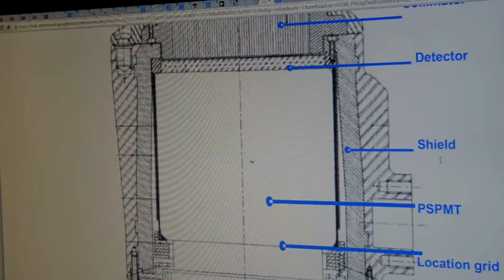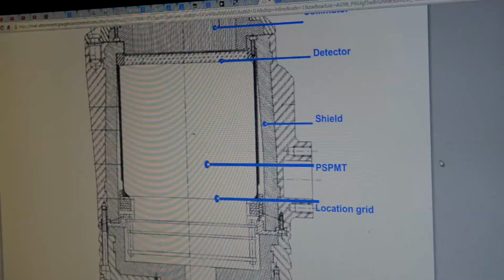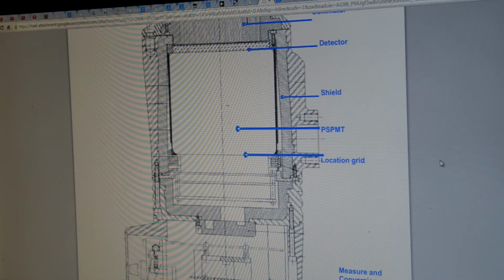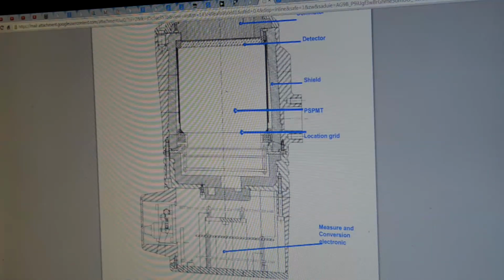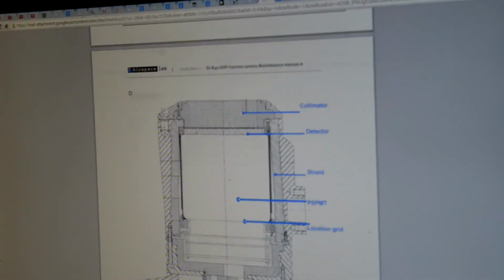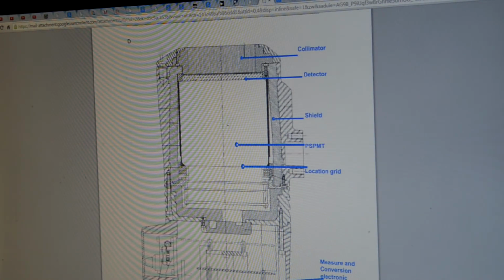Understand how the structure works by looking at the cross-section of the device. On the top, collimator, then detector, which is the crystal, that is in the heavy walls of lead housing. The big place in between is the photomultiplier, and then it's a location grid, phosphor screen, pixels made out of photodiodes. Each one will read the intensity of the light. The overall signal goes to the electronics, and through the fiber optic goes out to the USB.